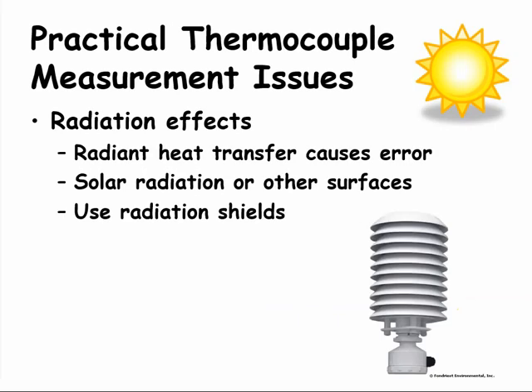The next temperature measurement issue is radiation effects. Radiant heat transfer can cause temperature measurement errors. The classic example is measuring air temperature outside. Solar radiation from the sun during daylight hours can distort the temperature reading if the sensor is not shielded. The same thing can happen at night on a clear night due to radiant cooling. Another example can occur when placing thermostats in a house. A thermostat should be located on an interior wall out of any sunlight.